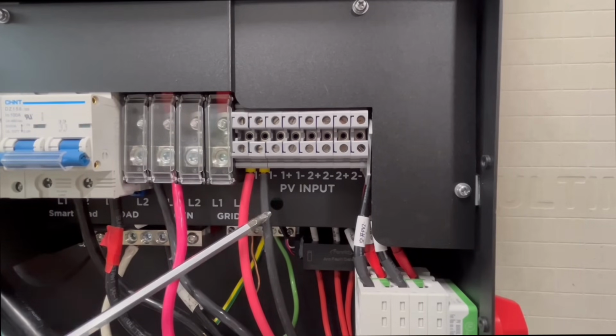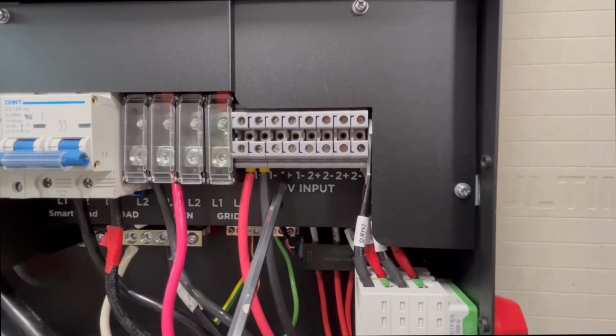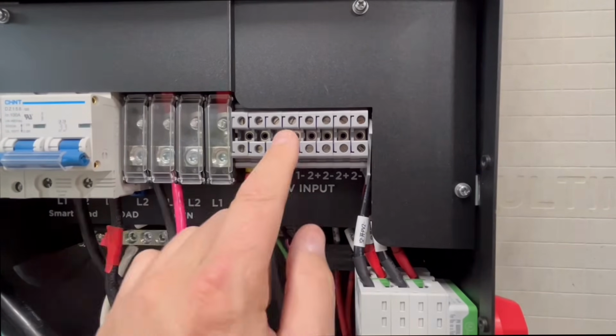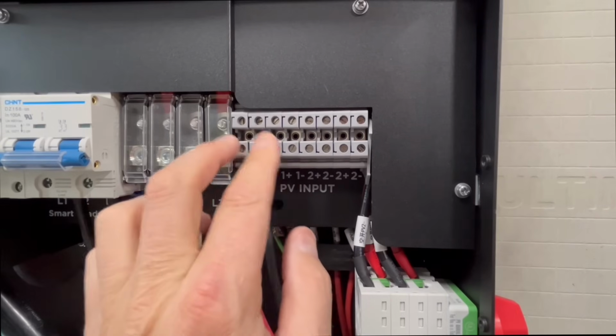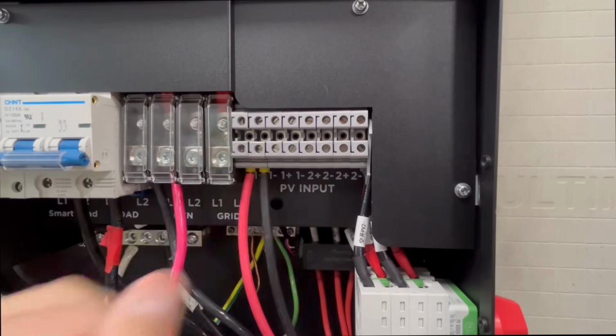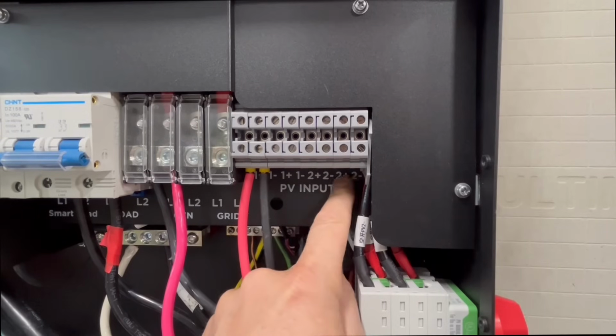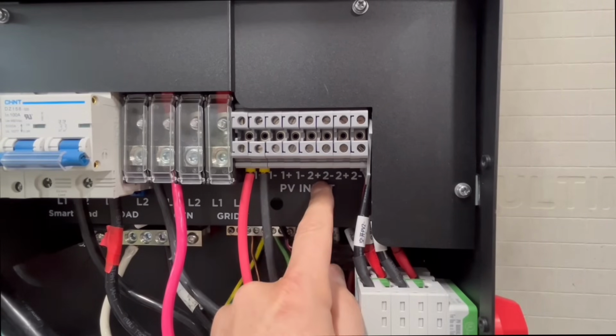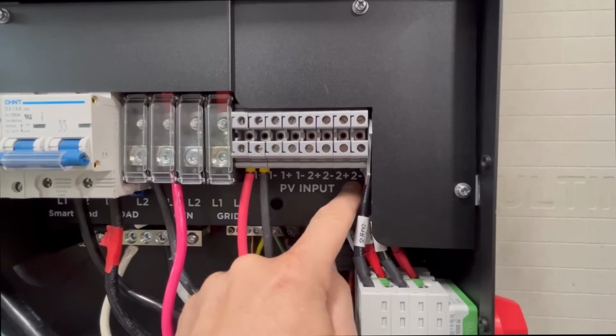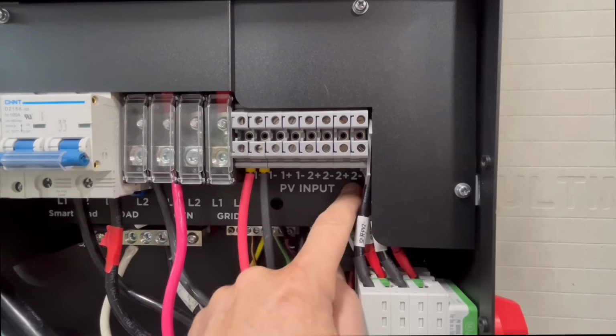And then the second string we're sending out of the combiner box is the 4,000 that we're basically just putting in there, like I said, to add fuses to it, another means of disconnect. And so that's going to go on PV1 as well. And then that would mean you have 8,000 watts and 4,000 watts, so you have 12,000 watts on MPPT1. And you'll repeat the exact same thing on MPPT2. This will be a combined string, and this will be an additional 4,000 watts.